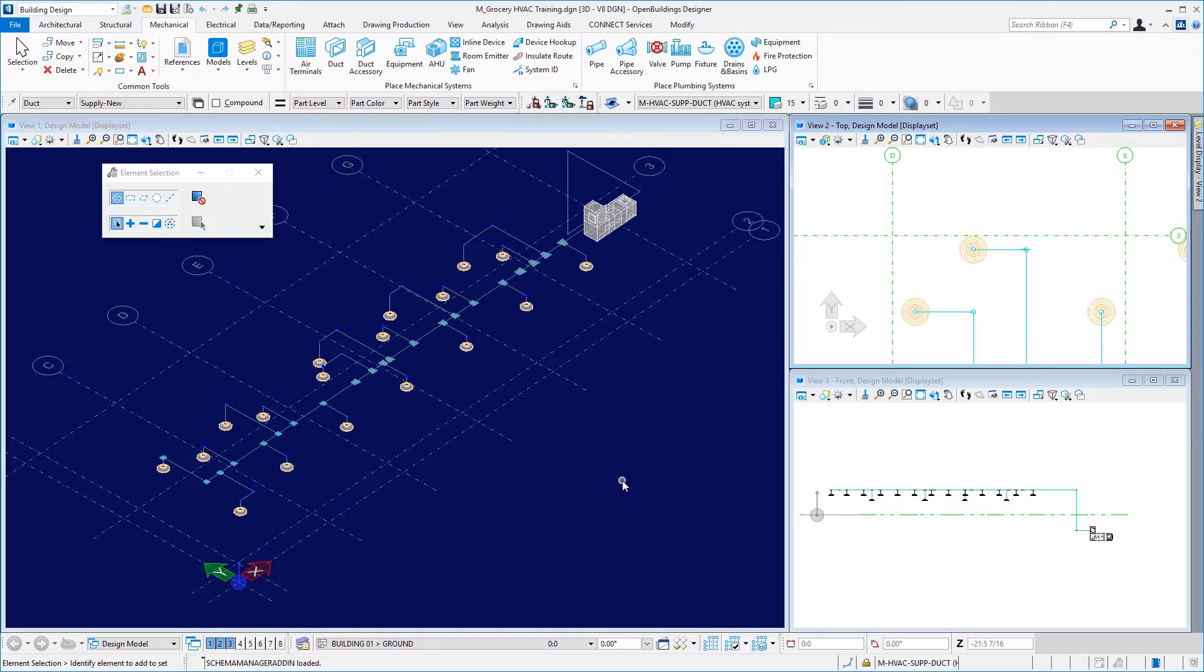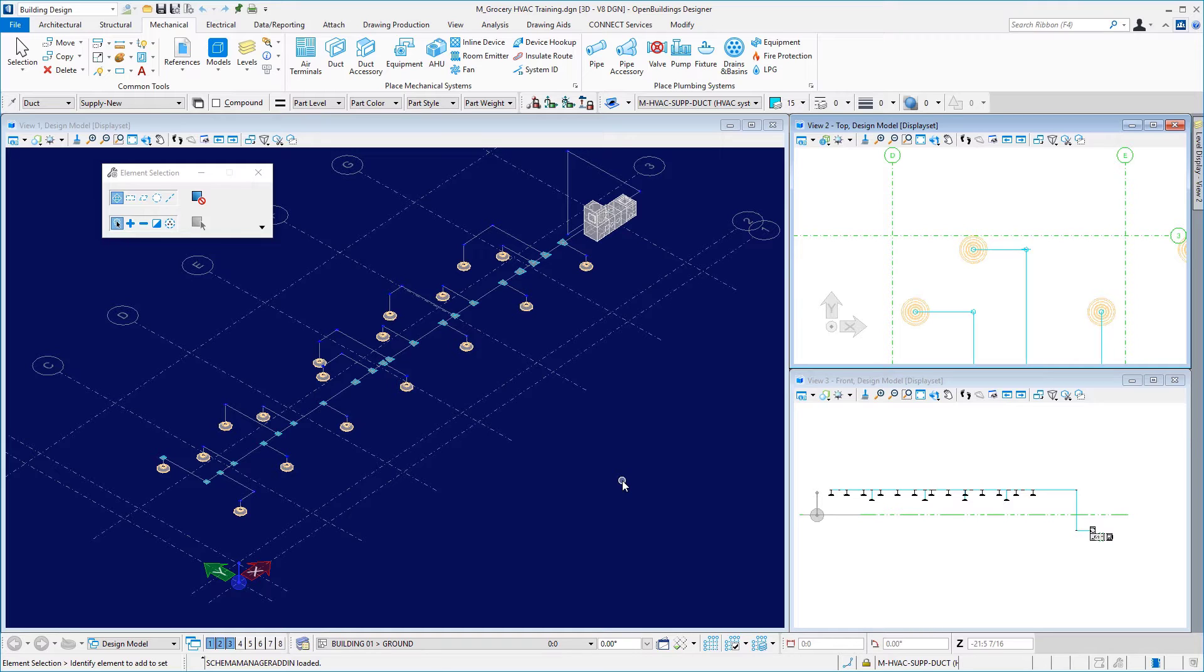Now, in order to run the duct sizing analysis, a complete route needs to be available in the current model. The terminal units, grills, diffusers, or plenum boxes in the route must have a value for the air flow rate data group property. So, let's take a look at the duct system sizing and analysis utility.